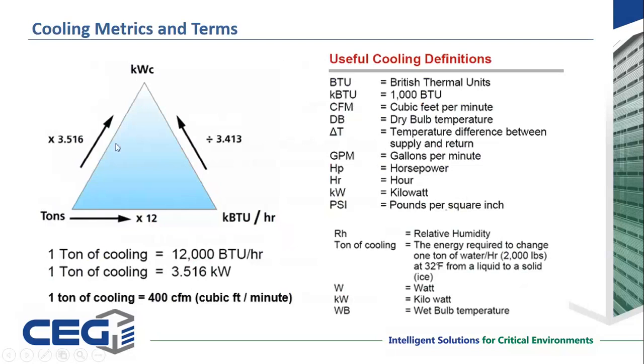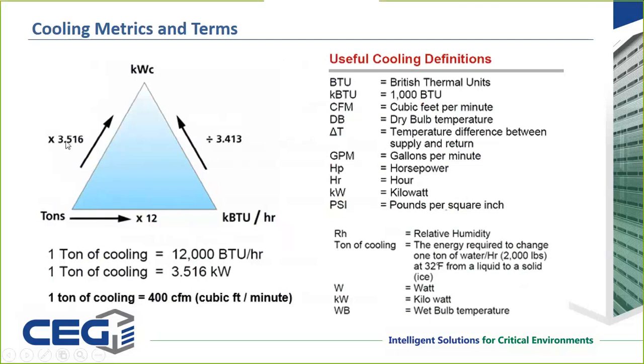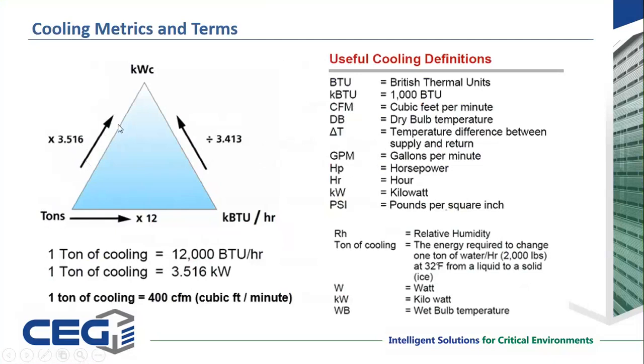But looking back at the triangle, what's most important is taking tons to kilowatts, which is a multiplication of 3.516. I always kidded our sales reps that you need to memorize your 3.5 times tables. Because when you get into a data center and someone says, 'I have a 30-ton air conditioning unit,' you can quickly do 30 times 3.5 and figure out how many kilowatts of cooling that air conditioner is rated for. Then things start to make sense when they talk about how much IT load they have in the space.